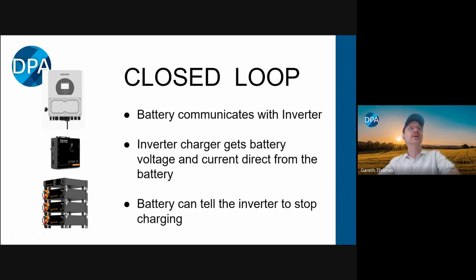The other big advantage to closed loop is that it allows the batteries to instruct the inverter to do dynamic charging. What that means is that when the batteries get towards the top of the charge cycle, they want to balance the cells so that the cells are all at the same voltage point. And it does that towards the top of the charge cycle, so it wants to slow down that charge cycle so that it can do the balancing. With open loop, it's not able to do that. The inverter is just going to charge it as quickly as it can. Whereas with closed loop, if the battery bank wants to, it can slow that charge rate down in order to allow it to have more time to balance itself. And that's going to mean you have better health of the battery system going forward, because it's going to be more balanced.